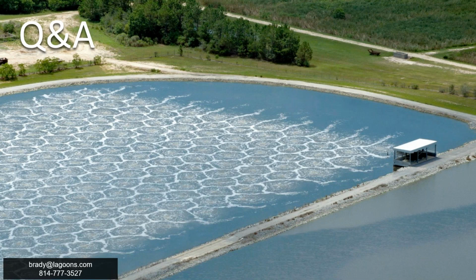We have some turbo blowers installed in northern Minnesota, and I know you're talking about Canada, but Minnesota is about as Canada as we get in the United States from a people and temperature standpoint. Those blowers are running great. They're super happy about it. I have not seen any issue. They're placed in a building, piping exterior air into the building, and they liked it so much they bought another one. So I'm not seeing that as an issue, but I suggest you talk to your blower manufacturer about that one.